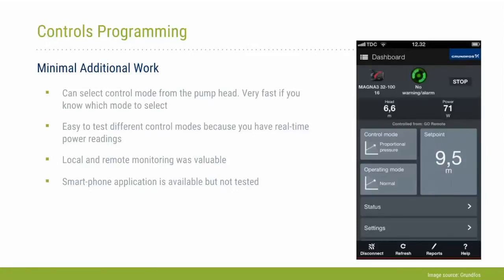As Jesse alluded to already, the pump contains all of the internal controls that are required. This is a representative example of that display. You can take the control mode, and then you get live feedback from the pump as to the actual power it's consuming and the differential head pressure that it's reading at the same time, as well as all the other sensors that are built into the pump. So you have the ability to change those control modes as necessary and tune that process to your application based on what you're going to get the best performance with.